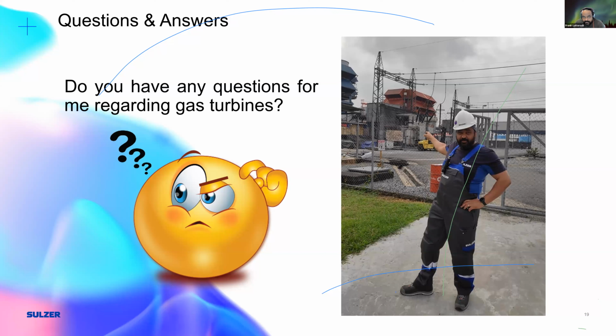Thank you for the question. With regards to Nigeria, I would not recommend anything with too much electrical output. Reason being, you do have situations where your gas turbine goes down. So are you able to stem a 300 megawatt loss if your unit goes into an outage? I would rather recommend smaller units. You could have maybe 140 megawatts as a base load machine, and then smaller ones that can take over the load in case one of your units goes into an outage.